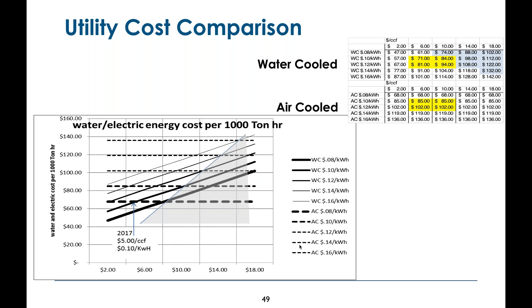Well, certainly working on the cycles of concentration, which involves more sensitive control and more attention to chemical treatment. Maybe there's a way to eke out a little more from your water treatment team. We always wonder why we can't use that blowdown water for some other valid use. Problem is, it doesn't grow green grass very well, and there isn't a heck of a lot else you can do with it. So I talked about reducing the cooling load, big effect.